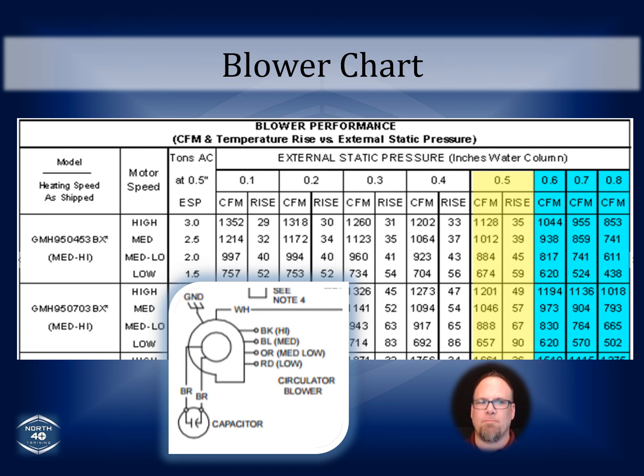If you don't do that, what happens? If you don't set up your blower speed properly, well, then what? I'll be honest with you, I went over a decade not understanding any of this stuff. So what happens to those air conditioning systems? Well, almost every one that comes from the manufacturer has high speed as your air conditioning speed. If high speed is your air conditioning speed, and that's way more CFM or airflow than what the system actually needs, what happens is it makes your coil too warm.